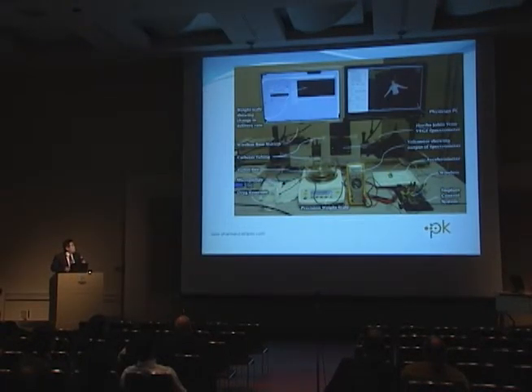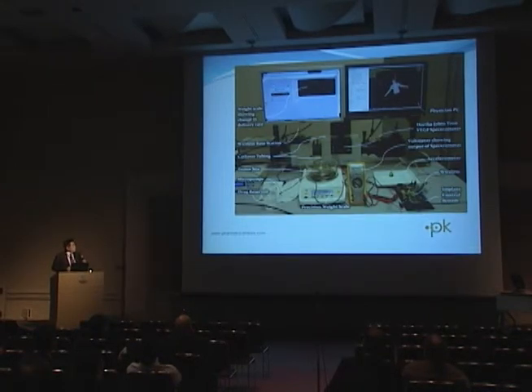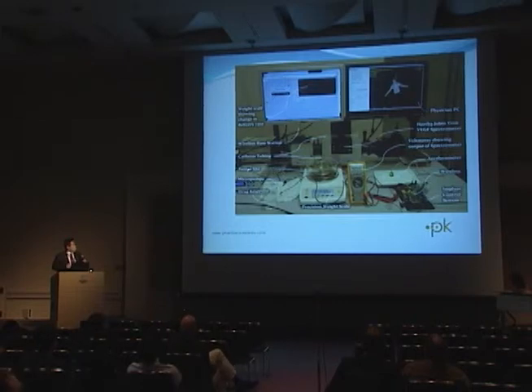And currently, the status that we're at is that we are in the process of miniaturizing this pump. But what we have done is essentially built a benchtop model of how this pump would go. And so this is the pump that's delivering the fluid, and it's going into a reservoir here from which we measure the weight, and then we can measure the delivery at which that fluid is coming through. And then it's sucked back with a spectrometer for detecting VEGF levels. And then it's controlled by this internal control system that allows this system to be directed in and out.